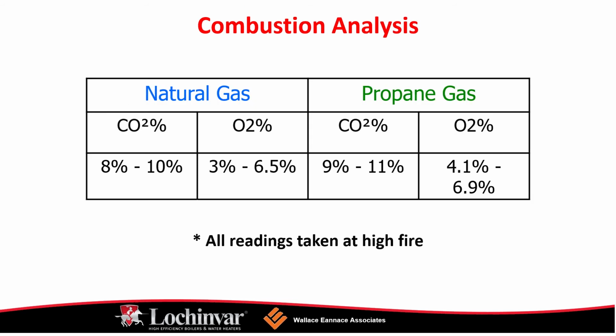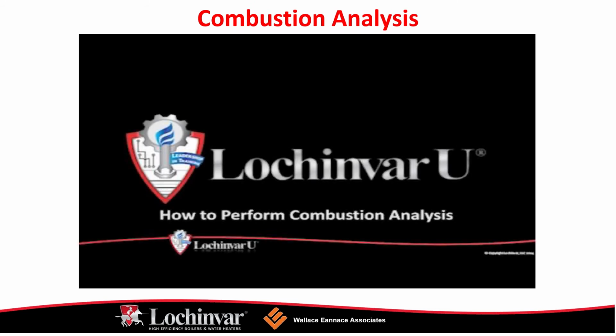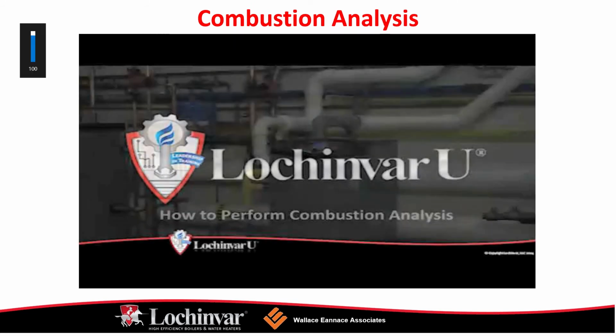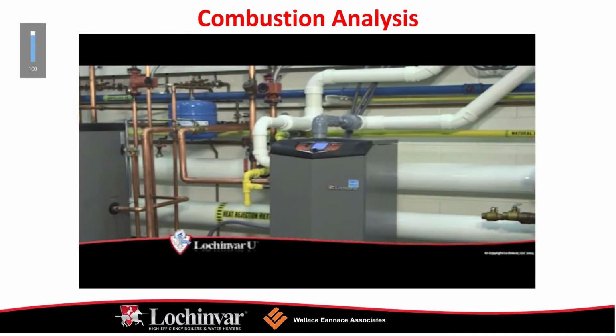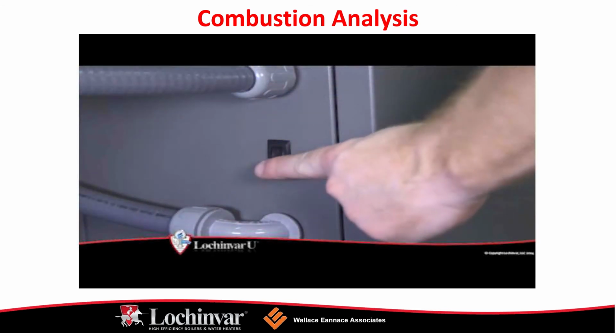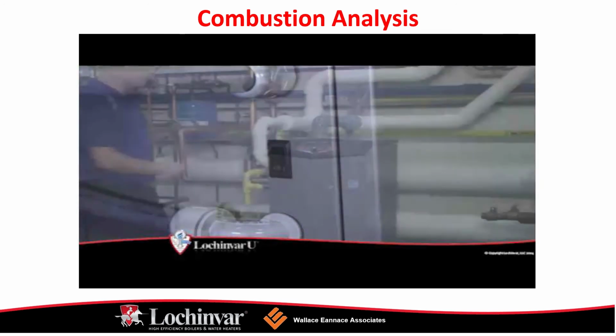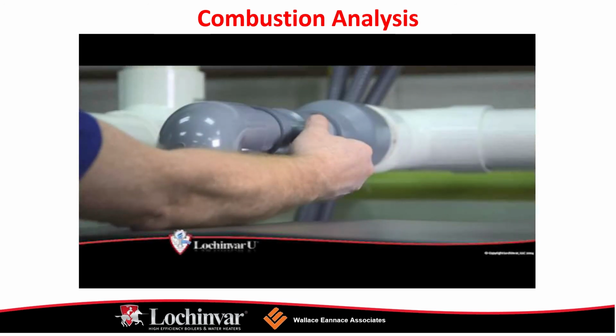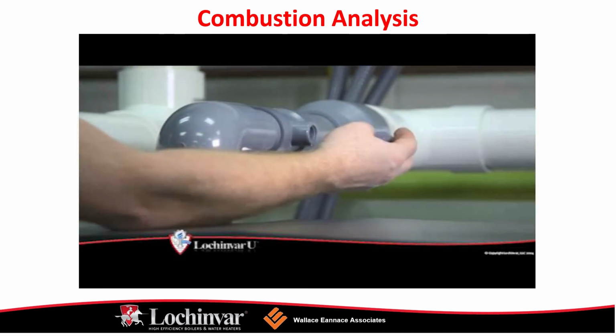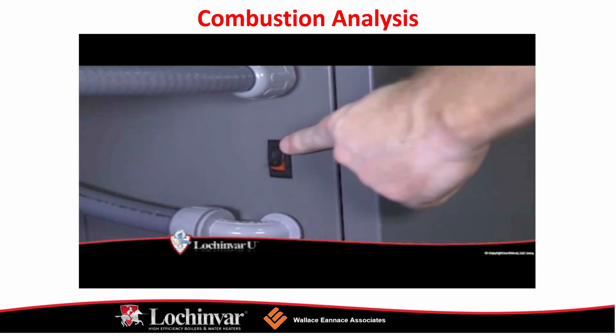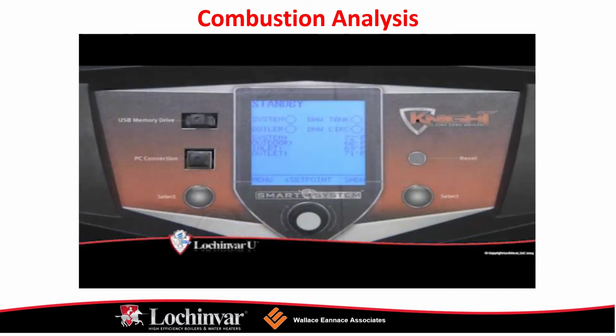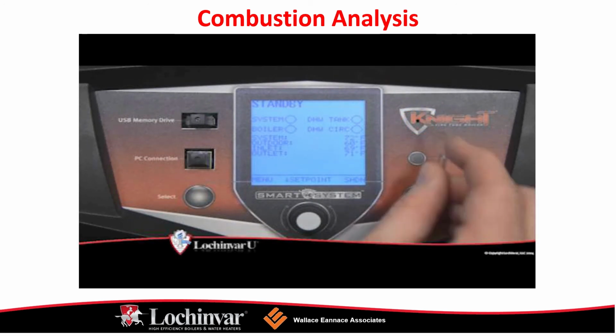Okay, combustion analysis. As all the videos have shown, we have to turn the main power off to the unit. I think everyone has that by now. We do want to remove the flue temperature sensor from the flue pipe connection, obviously turning the main power back onto the unit, and then place the unit into standby mode by pressing the shutdown button on the display.